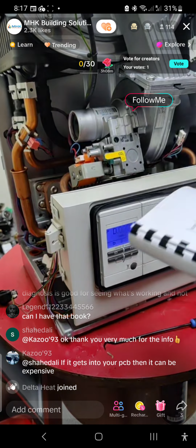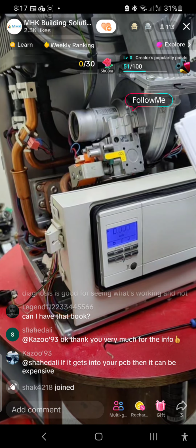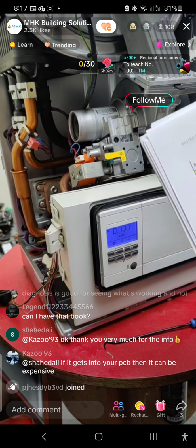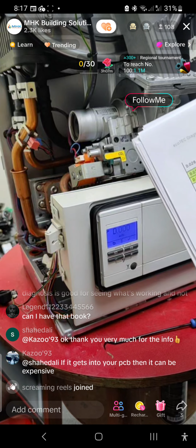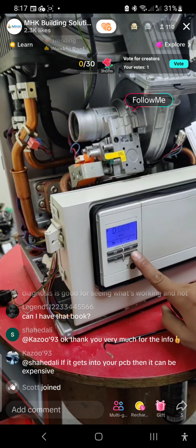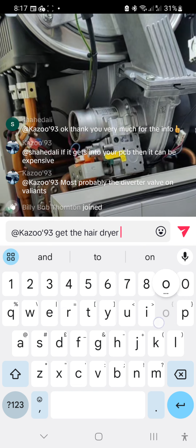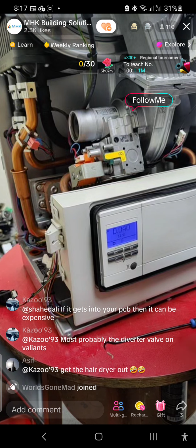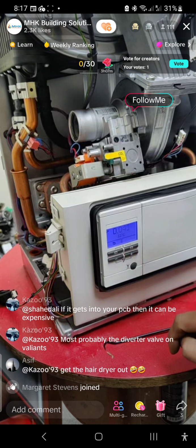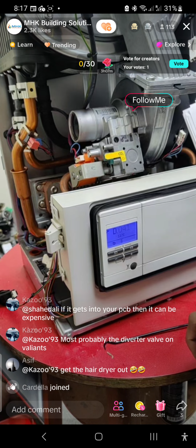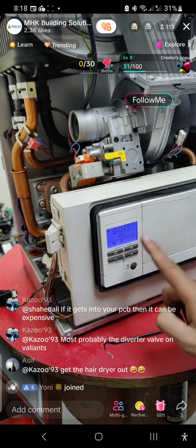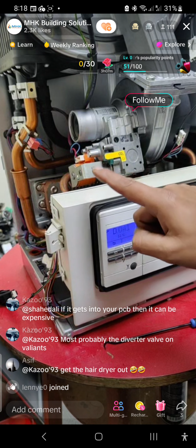Let's have a quick look at those, because that's handy if you're trying to do some fault finding. D40 is primary flow NTC temperature, and D41 is the return one. So D40 should be around 7-8 degrees, I would imagine. 11 degrees - D40 is reading 11 degrees Celsius, and D41 is also 11 degrees. So this is what the PCB is reading those sensors as.